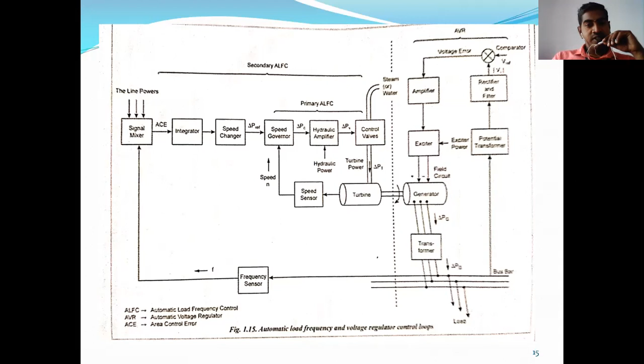In primary ALFC, the circuit primarily controls the steam valve system leading the turbine, which senses the speed of the turbine. This is compared with the reference speed governor, whose main activity is to control the speed of the steam by opening and closing the control valve if the differential speed is low. This controlled speed controls the frequency.